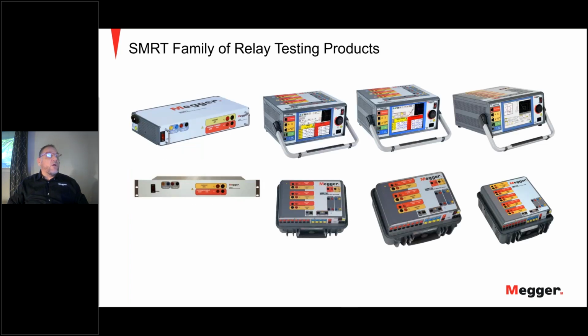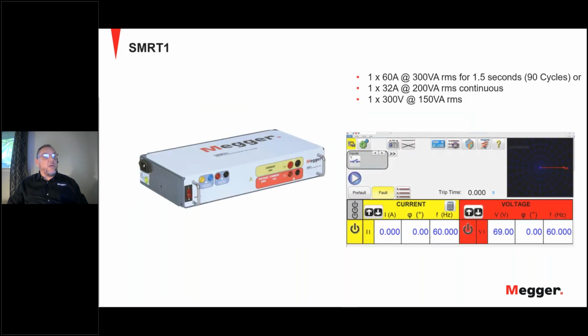Okay, so first of all, we are looking at the SMRT family of relay testing products. We've got a full lineup of SMRTs spanning from the single phase SMRT1 right up to multi-phase units like the SMRT 410 and 410D. Looking firstly at the SMRT1, it's a single channel unit with 1 voltage, 1 current source. Current can go up to 60 amps at 300 VA for 1.5 seconds or 90 cycles. The continuous rating for the current channel is 32 amps at 200 VA. The voltage channel is 300 volts at 150 VA RMS.